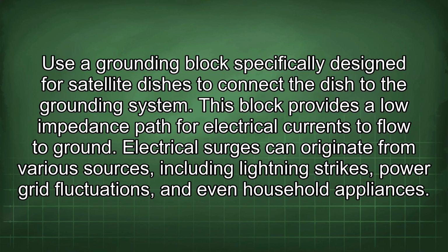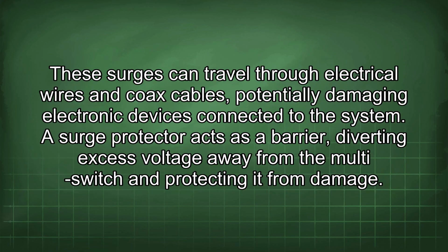Use a grounding block specifically designed for satellite dishes to connect the dish to the grounding system. This block provides a low-impedance path for electrical currents to flow to ground. Electrical surges can originate from various sources, including lightning strikes, power grid fluctuations, and even household appliances. These surges can travel through electrical wires and coax cables, potentially damaging electronic devices connected to the system.